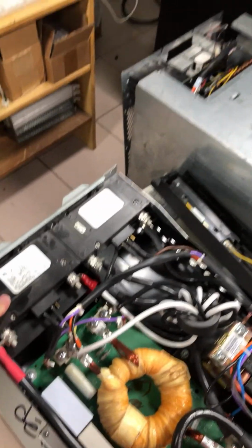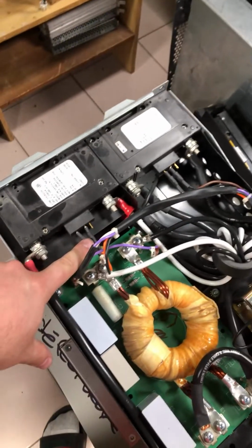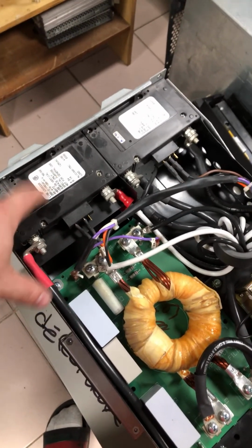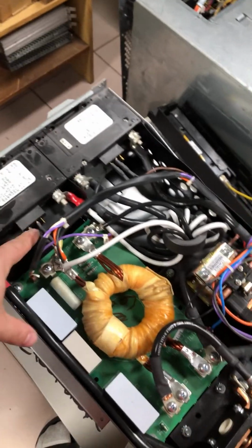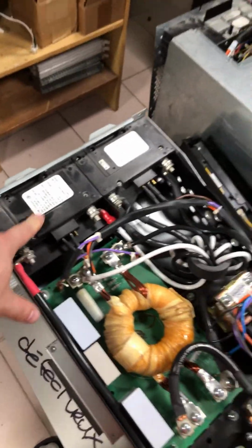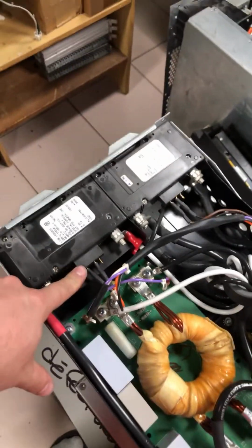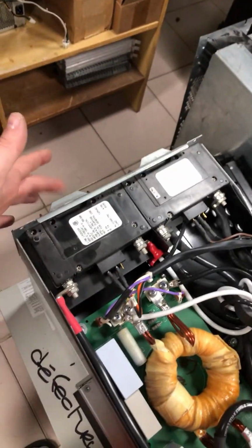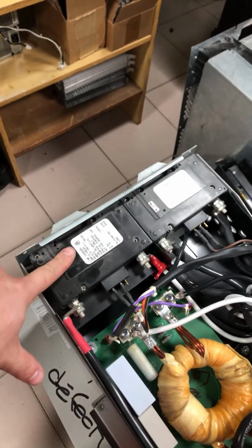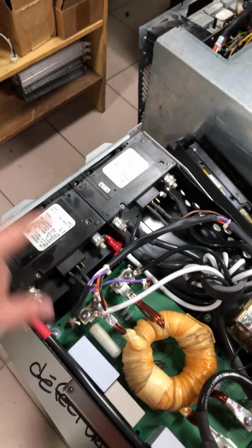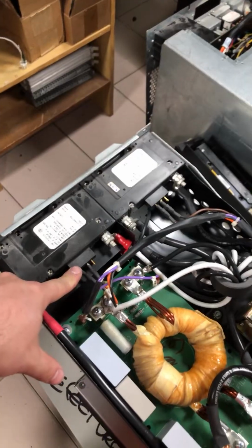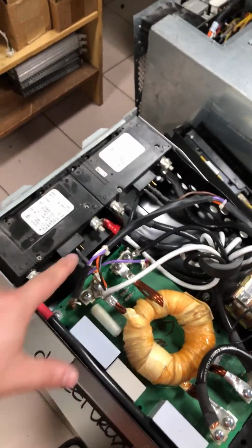I'm going to check here, because these are the two lines - this should be a switch based on what I saw on the sticker. It's a switch that opens and closes based on the position of the actual breaker. So if it's on, this is closed, and if it's tripped, it's open. That's how the unit knows whether it's tripped or not.